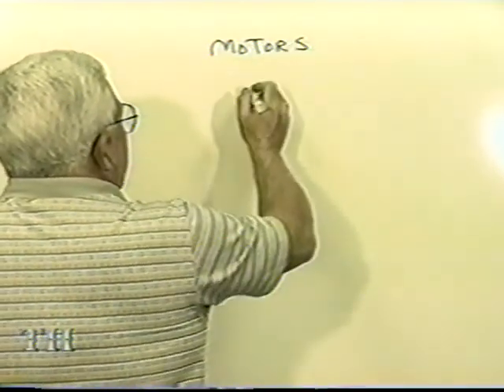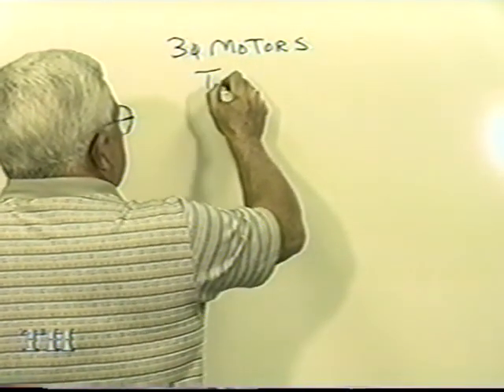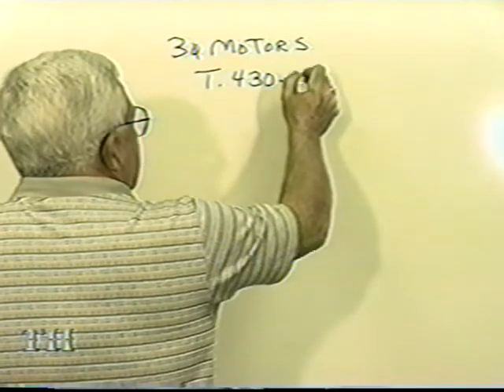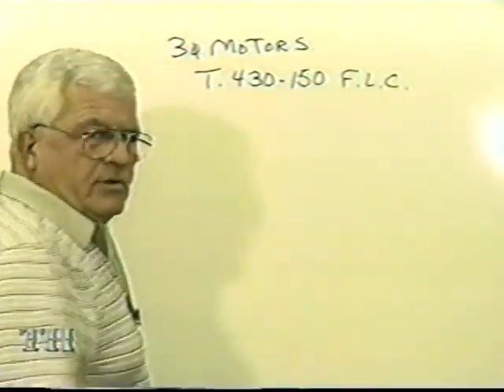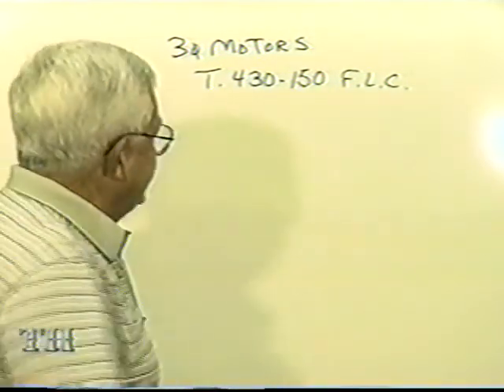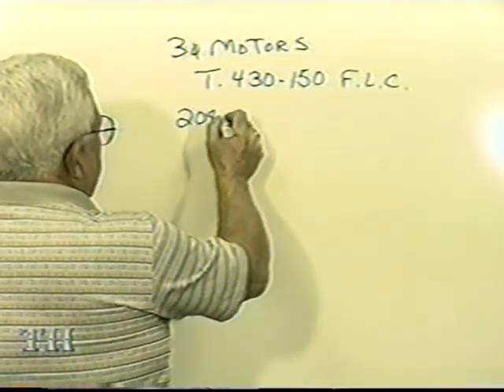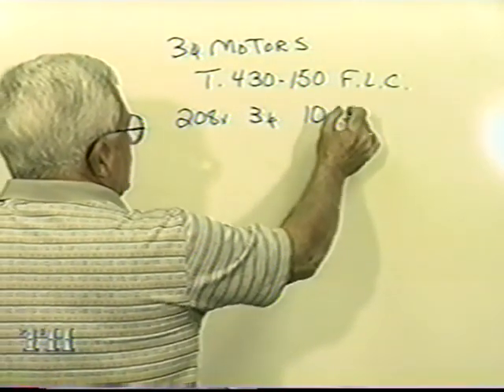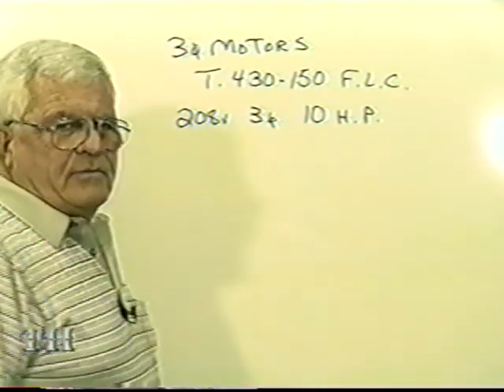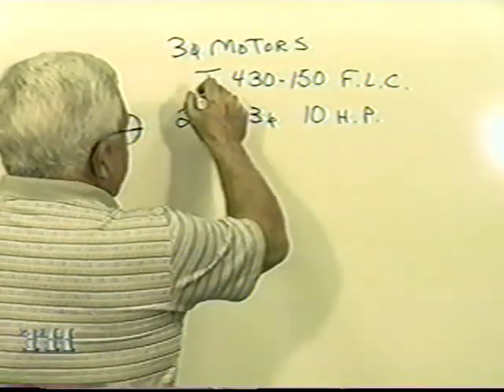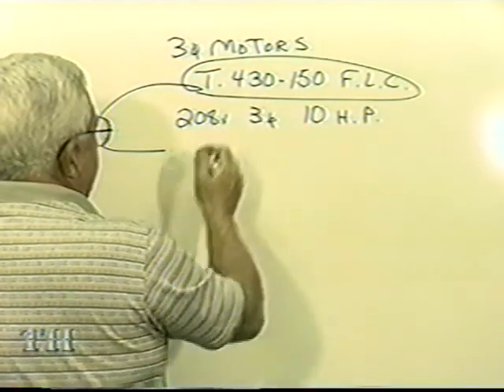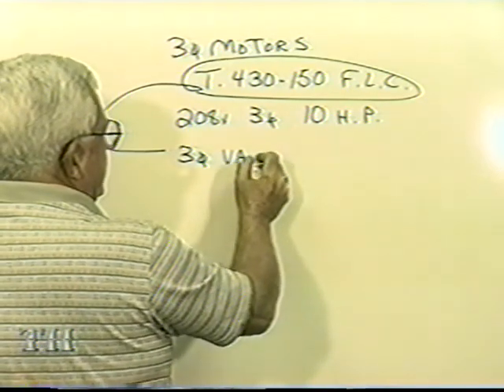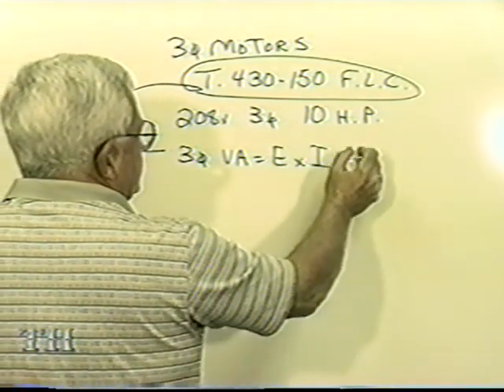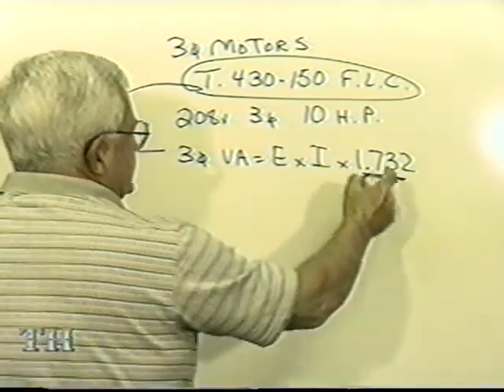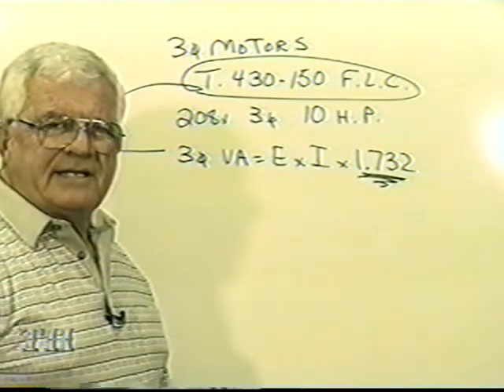We had a video on motors. And I said, well, for 3-phase, you'd have to go to this table, 430.150, for the FLC, the full load current. Well, they've asked this for 30 years. If you had a 208 volt, 3-phase, 10 horsepower motor, and they'd say, well, what's the VA? And I said on that video earlier on motors, right there is a good place to write 3-phase volt amps. You'd go E times I times the square root of 3. And I even said right here is what a lot of people forget when they talk about 3-phase. They forget that square root of 3.